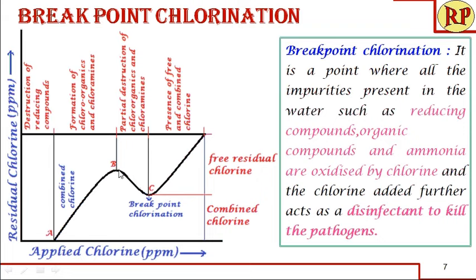Beyond B, as chlorine is added, the chloro-organics and chloramines are partially destroyed, so the combined chlorine slightly reduces up to point C. We call this the breakpoint chlorination point, because we assume that most of the reducing compounds, organic impurities and nitrogen impurities are oxidized. Further addition of chlorine beyond this breakpoint acts as a disinfectant to kill the microorganisms. Beyond C, this is free residual chlorine that acts as the disinfectant to kill the pathogens, so it is very important for us to identify this point.